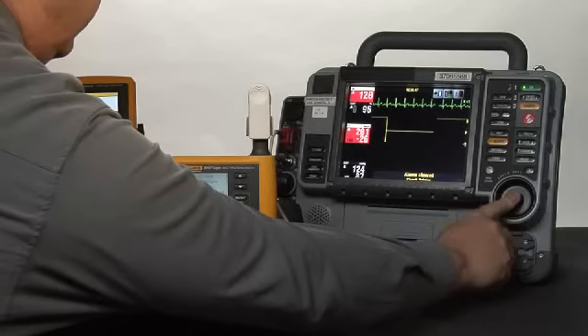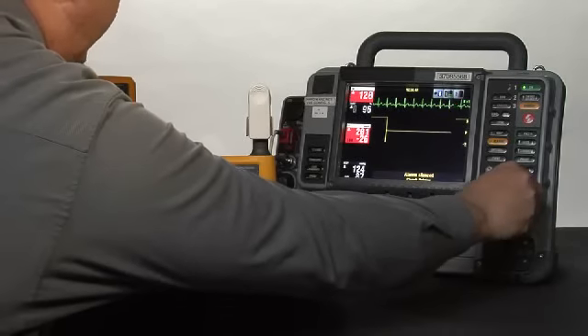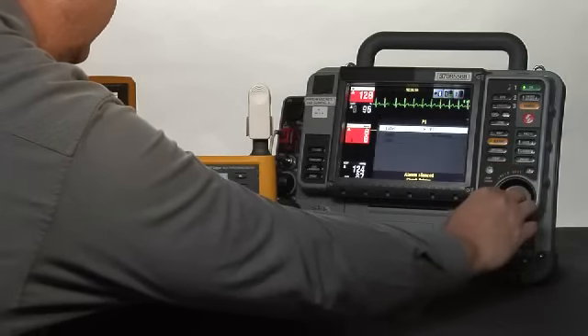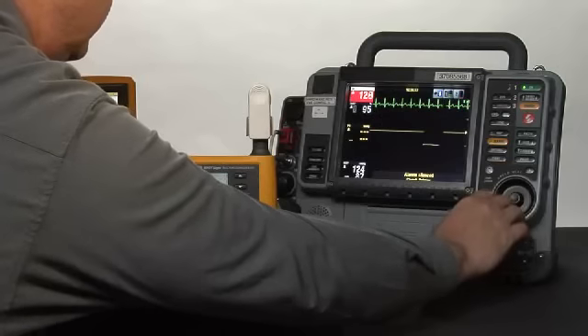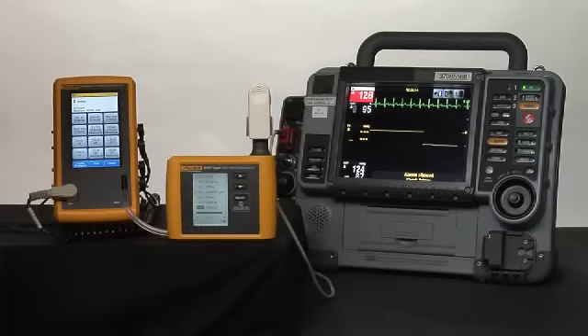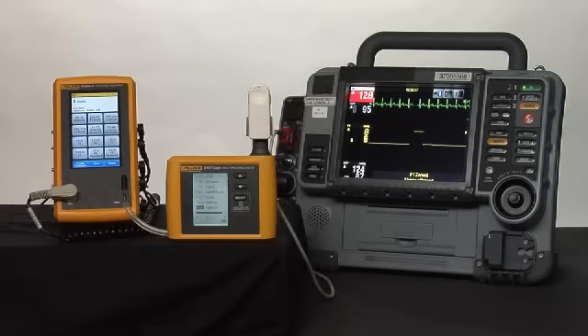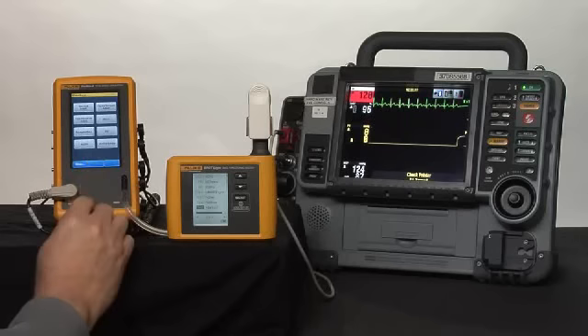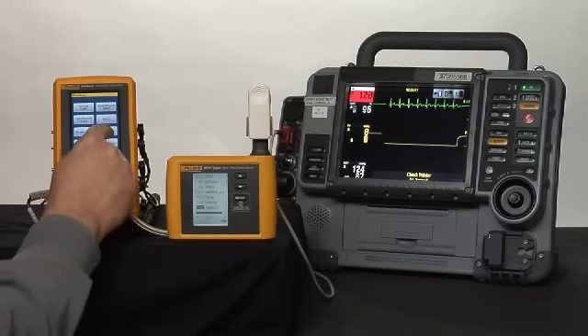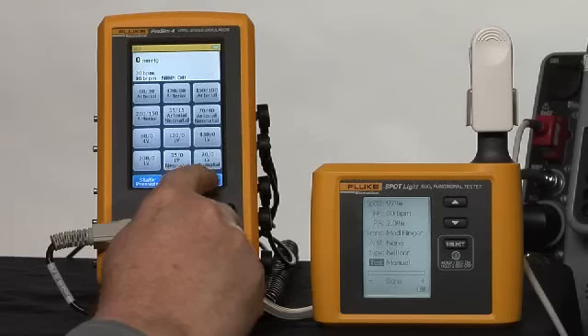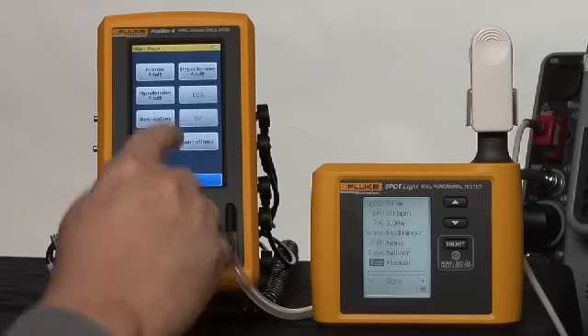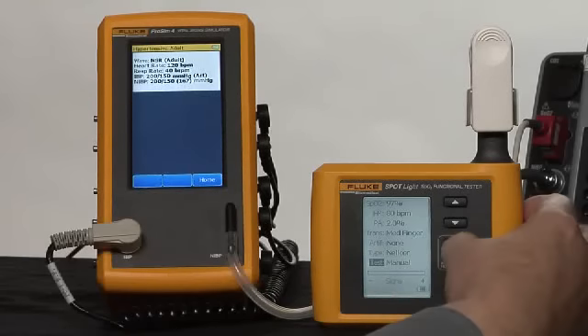Then on the clinical device, I will select my channel and zero the IBP channel. As soon as I have a zero, I can go on ProSim 4 back to the home screen, IBP to the home screen — hypertensive patient.